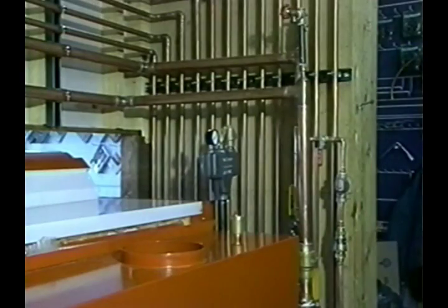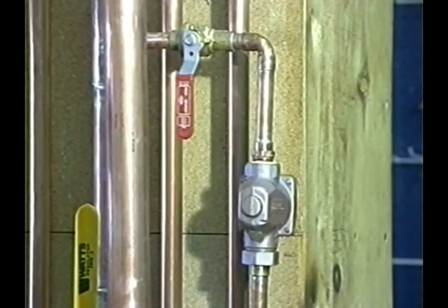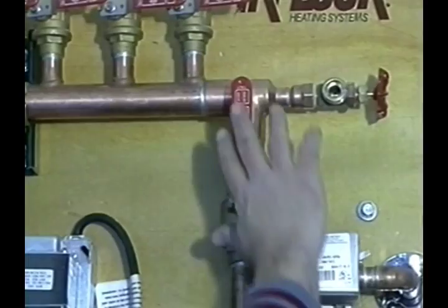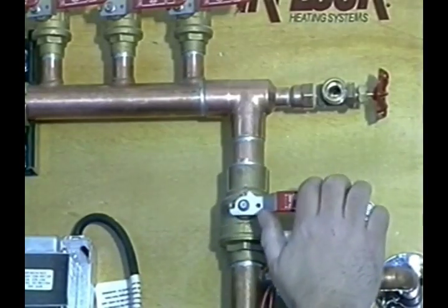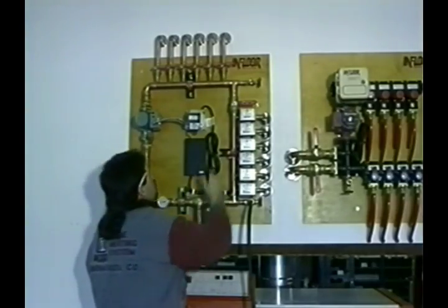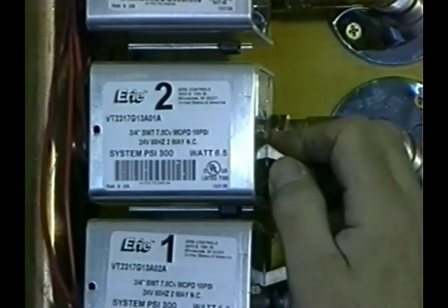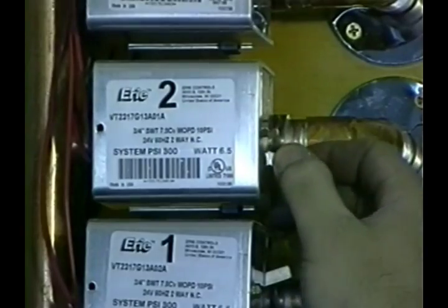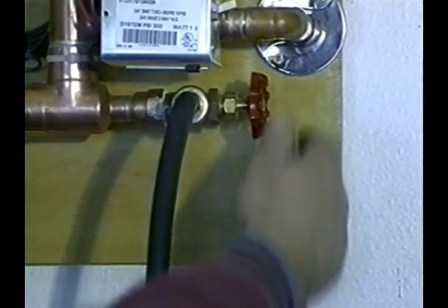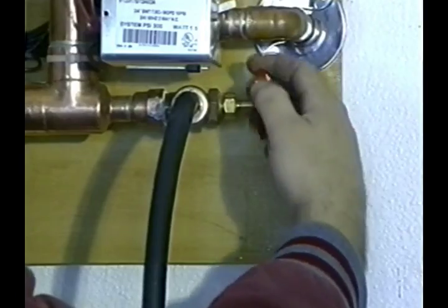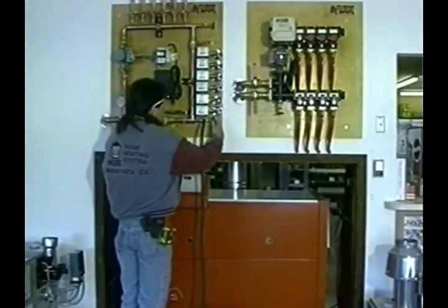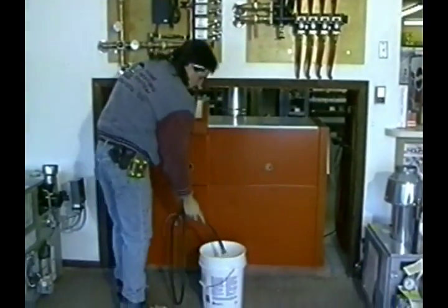The final phase of your radiant floor system is filling and purging. After doing a complete air pressure test to ensure no leaks exist, use the automatic fill valve to provide water to your heating system. Ball valves on the system should be opened or closed, forcing the water to flow from the supply side to the return side. A boiler drain on the return side of the boiler should remain open until a steady stream of water is flowing. Continue filling the system until the pressure is between 12 and 20 pounds.